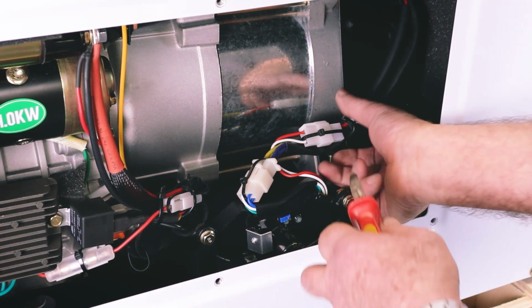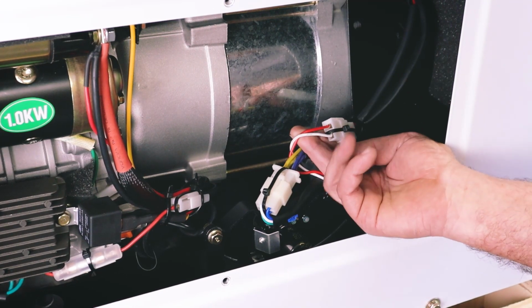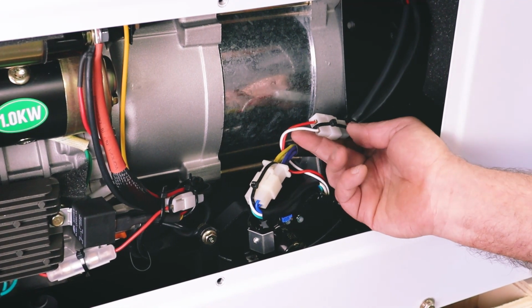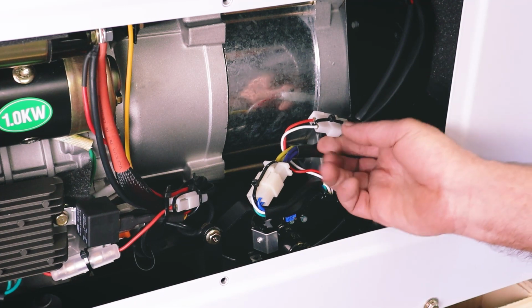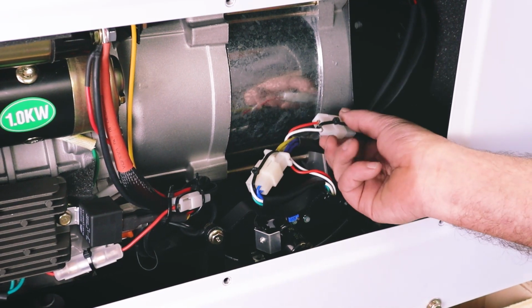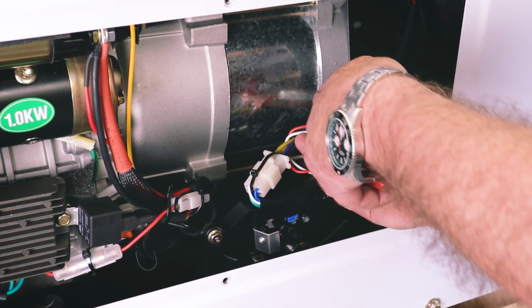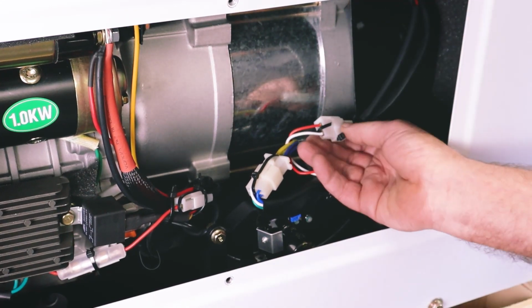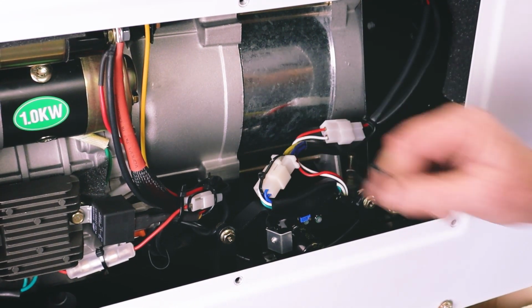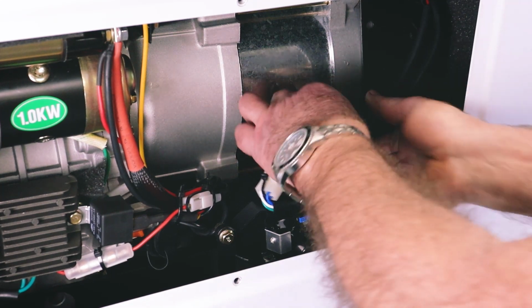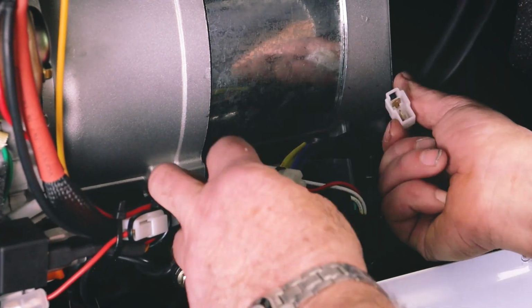However, if there's nothing visual, it could still be the AVR that's gone. So what I'm going to do is, you'll see one plug just has 2 wires on it, a red and a black. These may vary, but there's one with 2 wires and one with 4 wires. On a 3-phase, it might be slightly different, but there'll always be one plug with 2 wires. So I'll just cut the little cable tie off and disconnect the AVR.